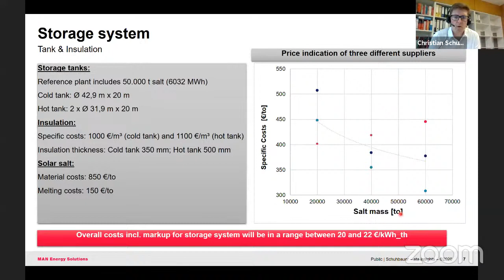The second point you have to consider, regarding the cost, is of course the insulation of the tank. Here you see the insulation thicknesses, which differ of course from cold tank to hot tank. And of course, one big cost driver is the salt itself. So the assumption here was 850 euros per ton for the salt and 150 euros per ton for melting up everything. You also have to consider that we have the foundation in the price here and all the civil costs and so on. So including markup for the whole storage system, we assume to reach around 20 to 22 euros per kilowatt hour thermal.